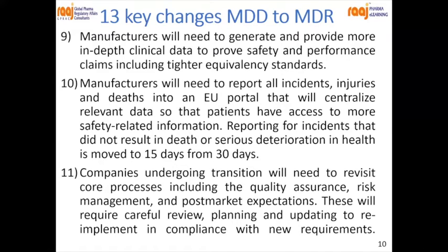Then manufacturers will need to report all incidents, injuries, and deaths into an EU portal that will centralize relevant data so that patients have access to more safety related information. Reporting for incidents that did not result in death or serious deterioration in health is moved to 15 days from 30 days.